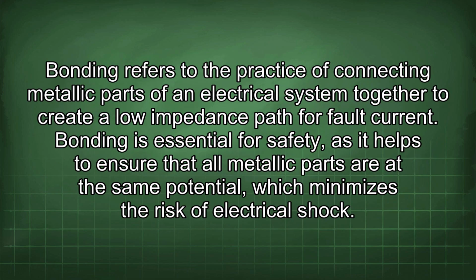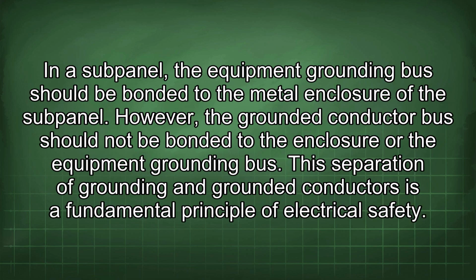Bonding refers to the practice of connecting metallic parts of an electrical system together to create a low impedance path for fault current. Bonding is essential for safety, as it helps to ensure that all metallic parts are at the same potential, which minimizes the risk of electrical shock. In a subpanel, the equipment grounding bus should be bonded to the metal enclosure of the subpanel. However, the grounded conductor bus should not be bonded to the enclosure or the equipment grounding bus. This separation of grounding and grounded conductors is a fundamental principle of electrical safety.